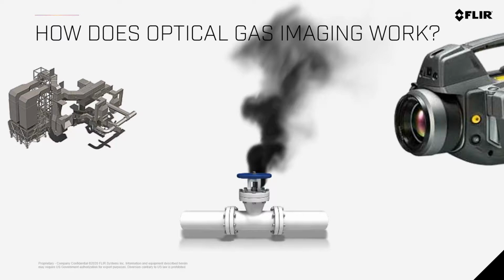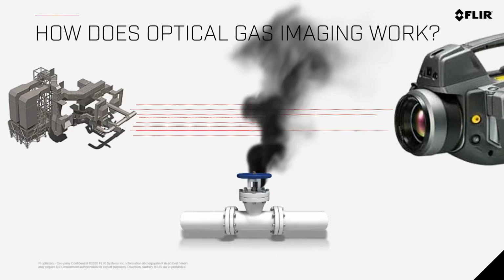So now when we have this gas leak coming through, only some of this pipe or this person, whatever it is, only some of that image is coming through. Everything else is going to be fogged out. It kind of looks like smoke, not necessarily smoke, but when you look at a bonfire at night and you see the smoke coming out, that's kind of what it's going to appear like on your camera. So this gas is going to block our IR detector, our lens, from seeing all those objects, and thereby we can see that there is a leak coming from this valve.